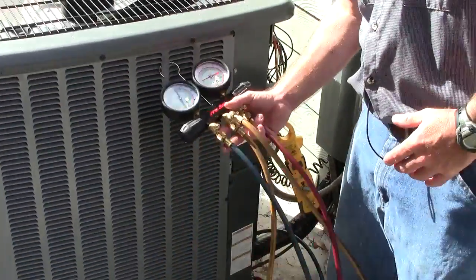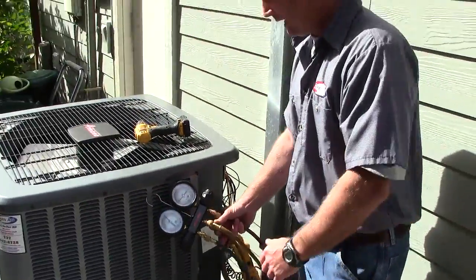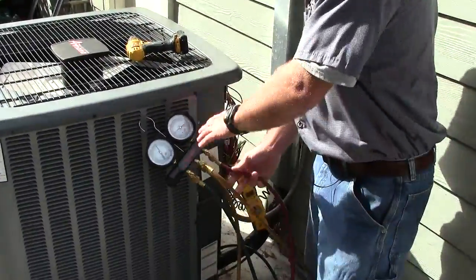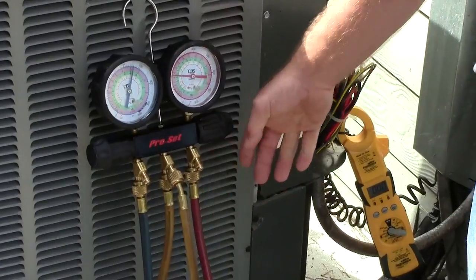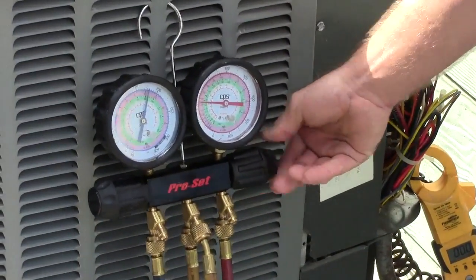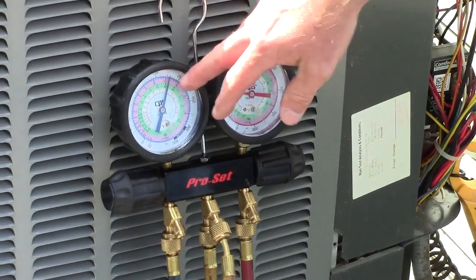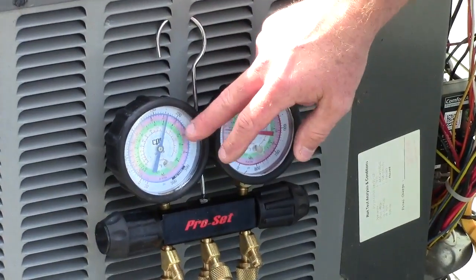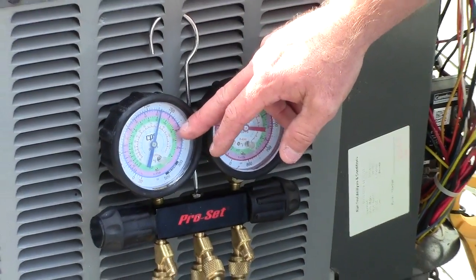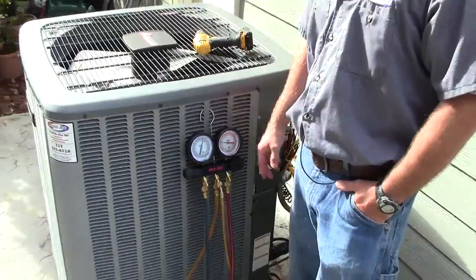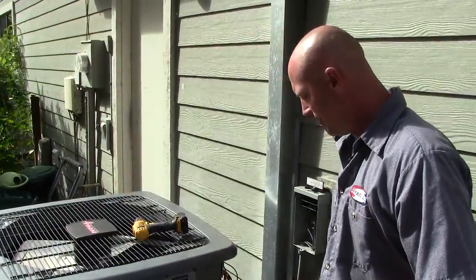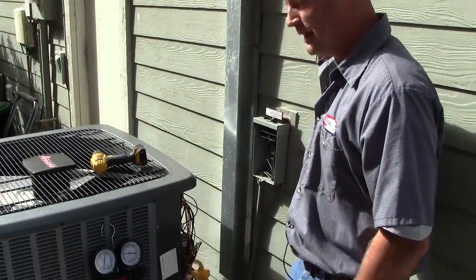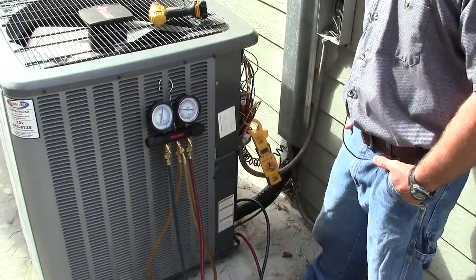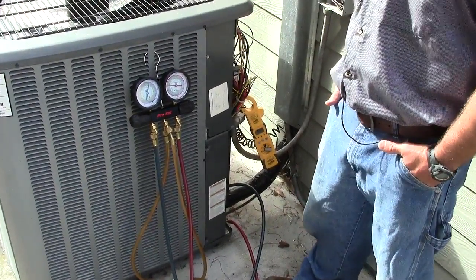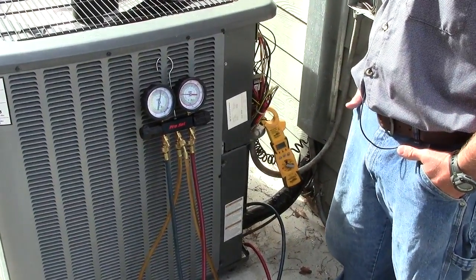On this particular unit, it's kind of difficult to see, but we have our gauges hooked up, and we'll make sure that when this machine's running in heat and cool that your pressures are correct. And by reading your pressures, we can also take other readings like superheat and subcool to make sure this equipment is running as efficiently as it possibly can. This particular unit, as we said earlier, is a heat pump, and it is important to check this in heat and cool when weather permits.